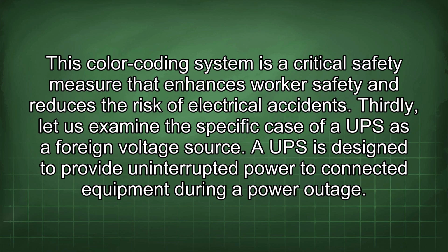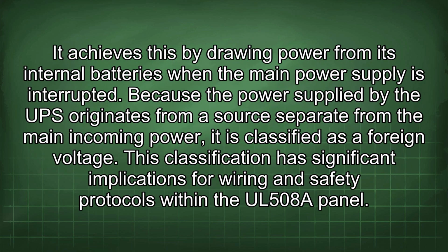Thirdly, let us examine the specific case of a UPS as a foreign voltage source. A UPS is designed to provide uninterrupted power to connected equipment during a power outage. It achieves this by drawing power from its internal batteries when the main power supply is interrupted. Because the power supplied by the UPS originates from a source separate from the main incoming power, it is classified as a foreign voltage. This classification has significant implications for wiring and safety protocols within the UL508A panel.